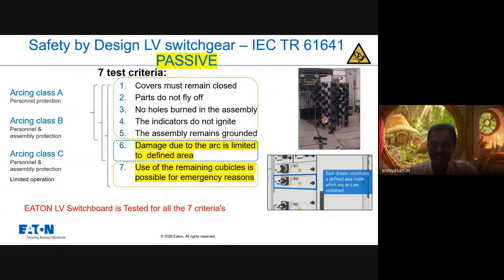Also, it should not create any holes in the switchgear, I mean in the external parts of the door or cover. If any holes get created, hot air or even flame will come out and affect the human being. Also, the ground earth continuity should be ensured. Suppose the internal arc happens in the cable compartment of one particular outgoing feeder, the arc should be confined within that cable compartment only. It should not spread to the nearby busbar compartment or breaker compartment. That is not accepted. Also, the rest of the cubicles should remain active so that we can put the switchboard back into service. The meaning is, except the affected compartment, the rest of the switchboard should be alive so that we are able to continue the operation.